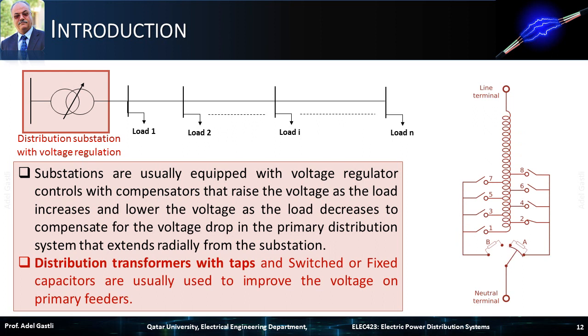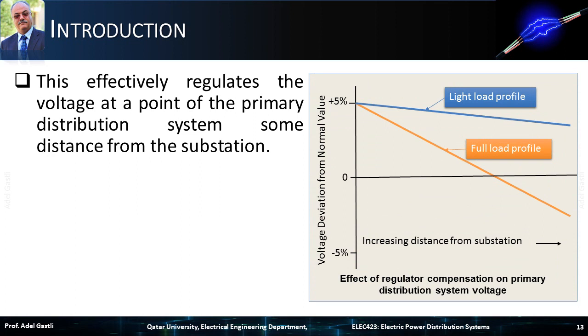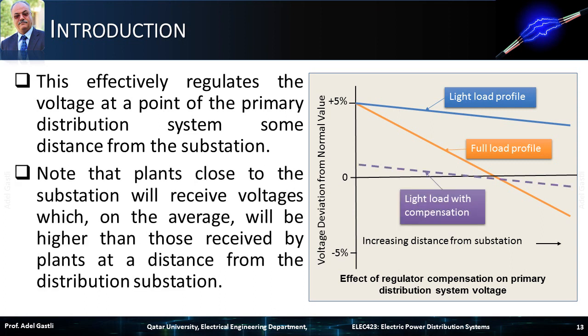Distribution transformers with taps and switched or fixed capacitors are usually used to improve the voltage on primary feeders. This effectively regulates the voltage at a point of the primary distribution system located at some distance from the substation. Note that plants close to the substation will receive voltages which, on average, will be higher than those received by plants at a farther distance from the distribution substation. In this figure, the dashed line in magenta color shows the regulated voltage with compensation for a light load. With voltage regulation and compensation, it is possible to maintain the voltage close to its nominal value, which makes the voltage deviation nearly equal to zero.